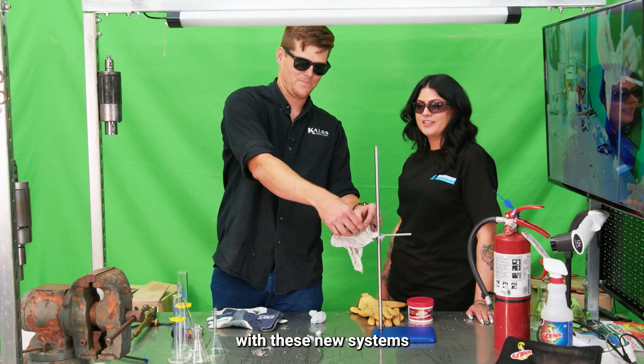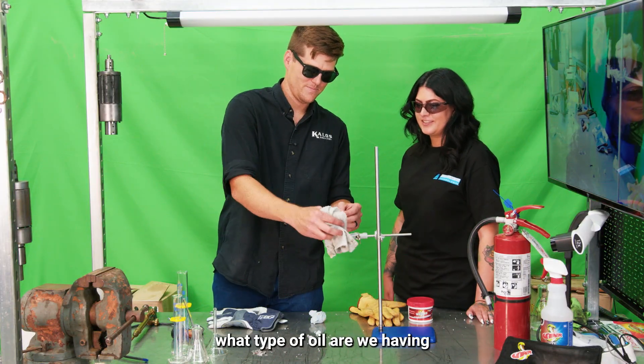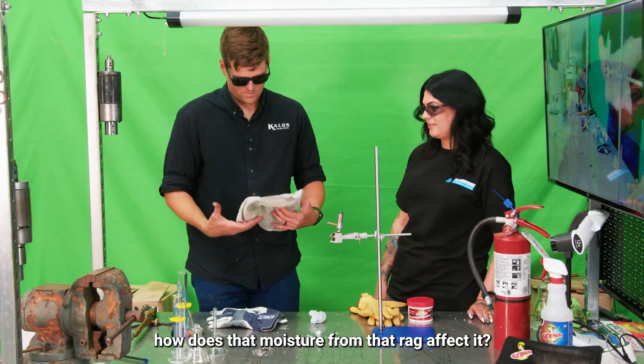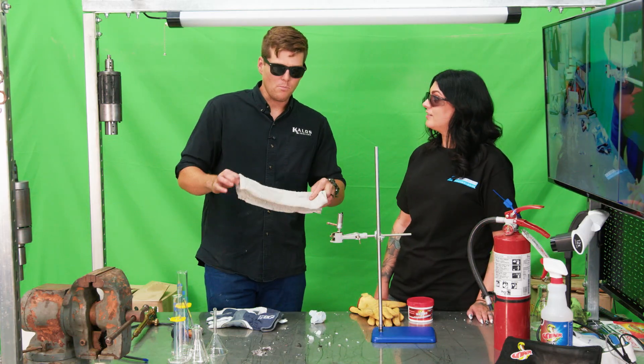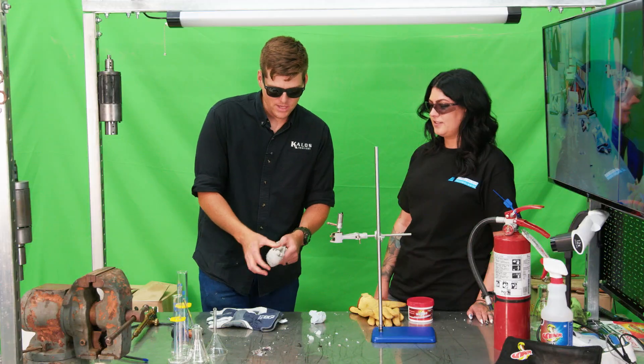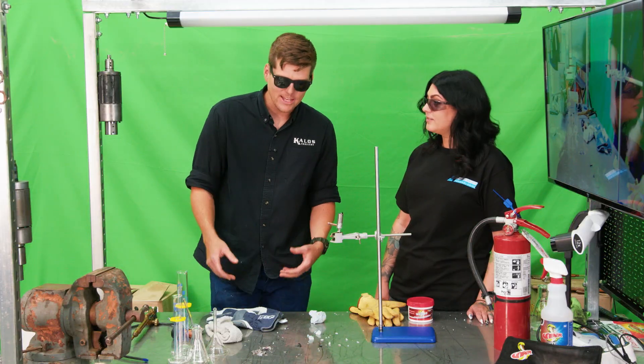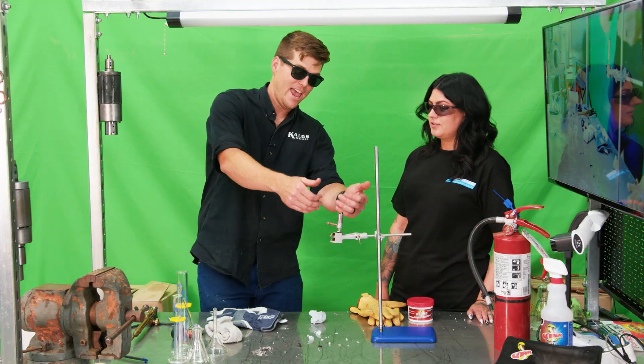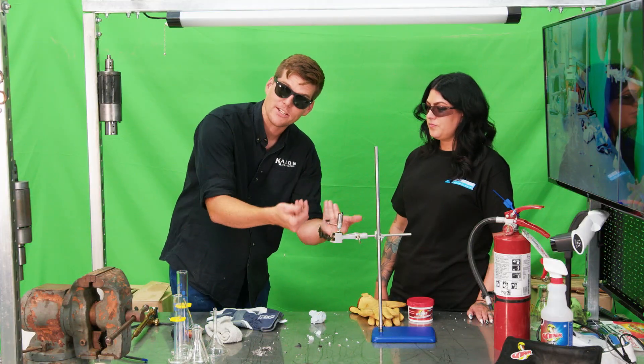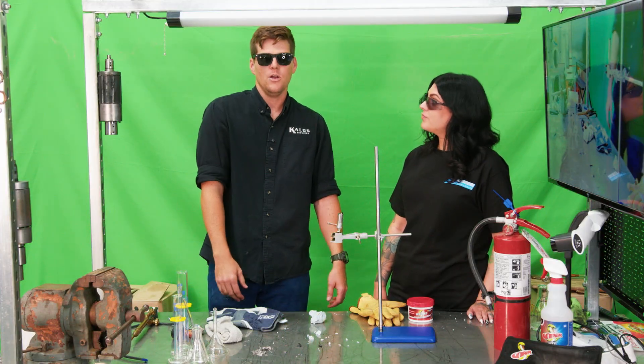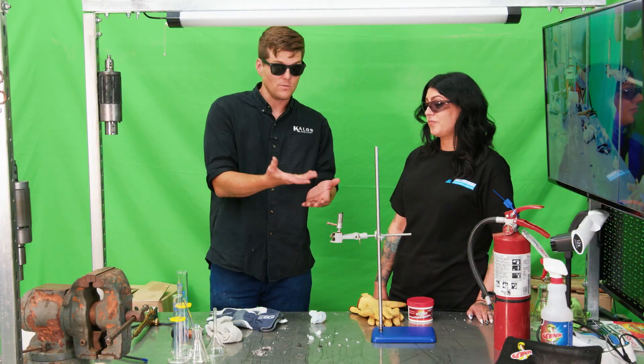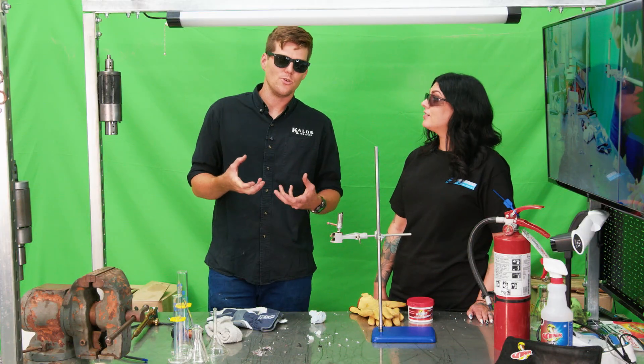Hey, Roman. With these new systems, what type of oil are we having inside of there? And how does that moisture from that rag affect it? So when we talk about moisture and oils like PVE oil or POE oil, if that gets introduced into the actual system itself, let's say that I'm brazing with a wet rag and the steam forces its way into my connection, which gets into my system.